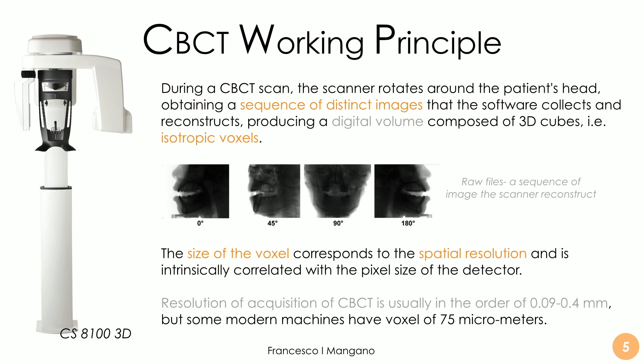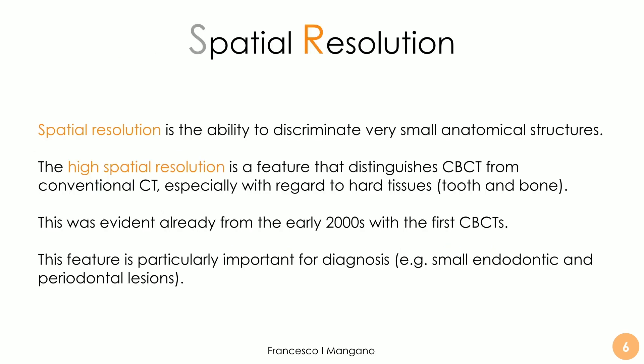The resolution of acquisition of CBCT is usually in the order of 0.09 to 0.4 millimeters depending on the machine. Some modern machines have a voxel size of even 75 micrometers — so a very, very small voxel. Spatial resolution is the ability to discriminate very small anatomical structures.